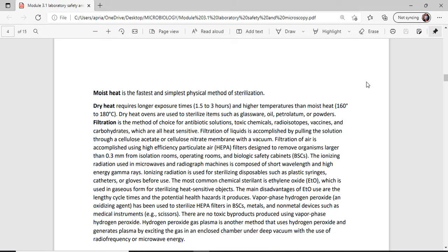items such as your glassware, oils, petroleum, or powders. When using dry heat, class, that's because if you use moist heat on glassware, you will see patches, white spots, when it dries. Then with oil, of course, you cannot mix it with moist heat, since moist means water, and you cannot mix water and oil. Also with petroleum, and especially with powders, since water cannot be mixed with powder.